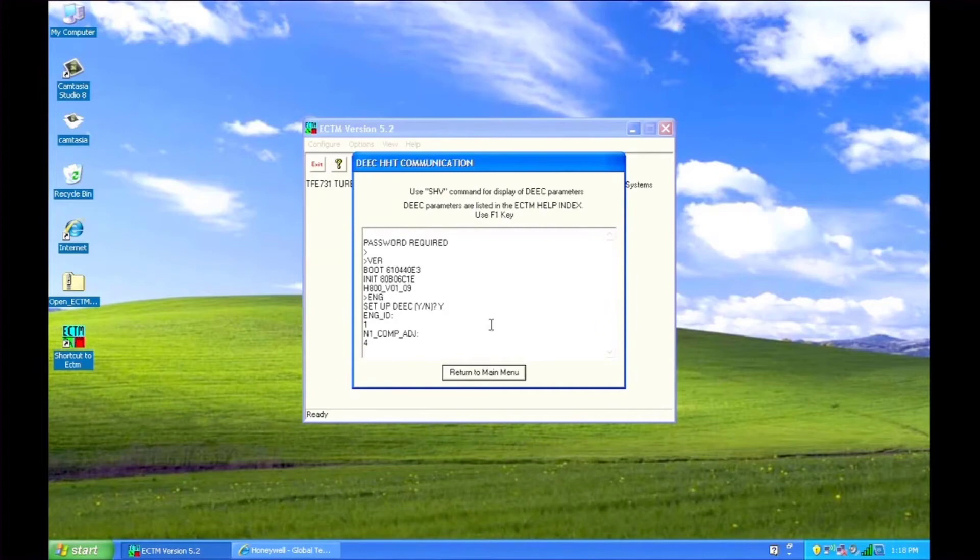Enter your engine ID code, compensation value, and specific gravity. Refer to the worksheet you filled out for this information. Make sure the MMSW setting is set to zero for auto mode. Push enter and return to the main menu.